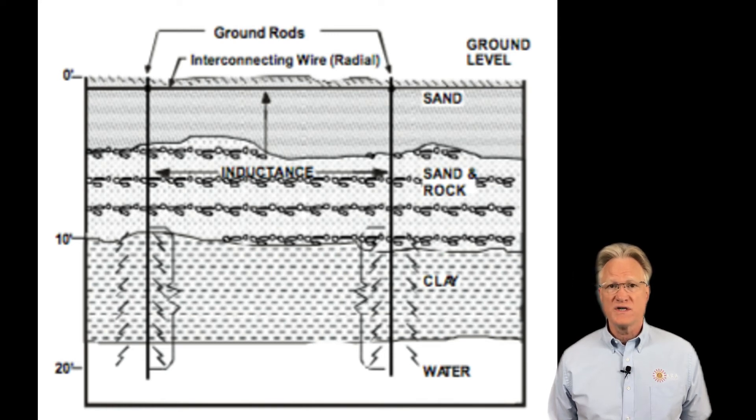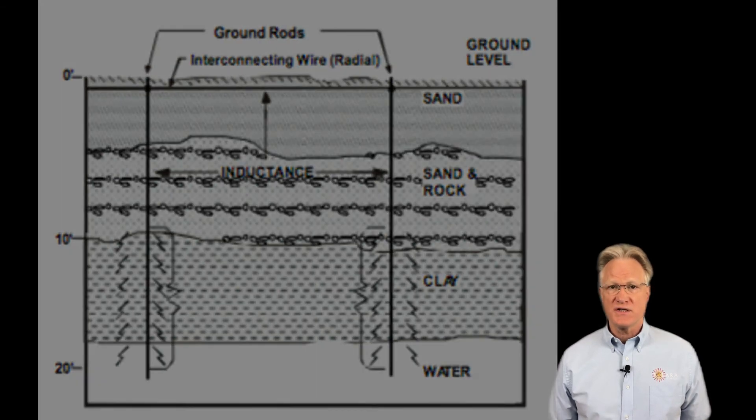Remember we want low resistance and low inductance. If we assume zero volts at the water table level—in this picture it's 15 feet down—then from the top of the soil down to the water table, the earth is a very poor conductor. Treating the soil is only half the battle. It only reduces the resistance.